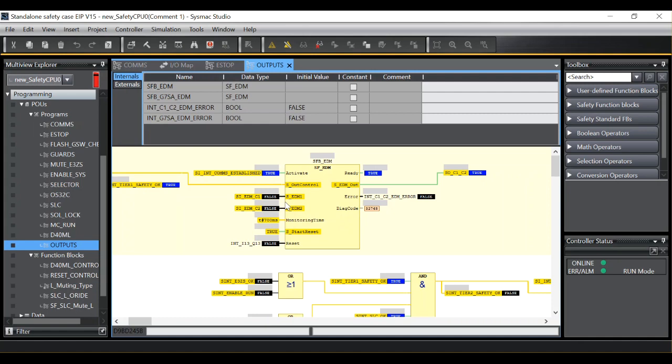If I trip my system now with an emergency stop you will see the results. So as the contactors come out we expect to see EDM 1 and EDM 2 go to logic 1. It is the inverse condition of the associated output.